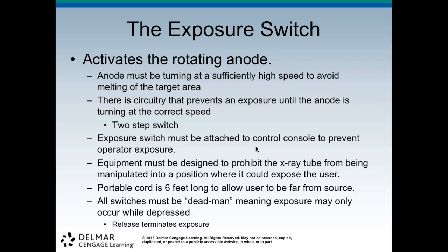So the exposure switch activates the rotating anode. The anode must be turning at a sufficient speed to avoid melting of the target. There is circuitry that prevents the exposure until the anode is turning at the correct speed. So it's a two-step switch. You know how you rotor up and then you expose, right? It won't let you expose until it's done getting the anode to full speed.